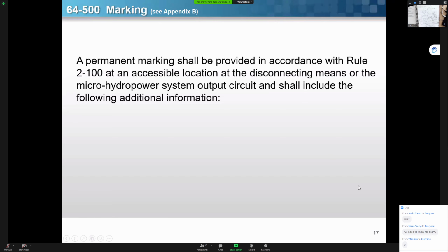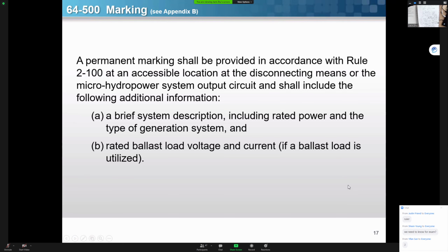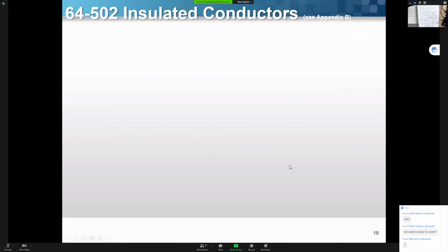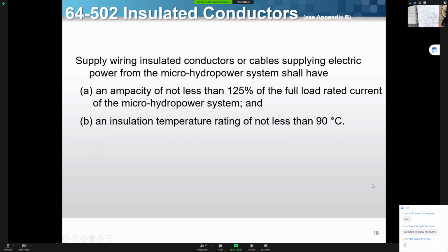This is talking about code rules. We're going to look at the code rules slightly later altogether. Here is something when we're talking about code rules, you will know. When you guys learned about motors in third year, you always learned the conductor capacity for continuous load has to be 125% of rated motor load, right? Here, the same thing for the generator, the conductor capacity is at least 125%. But in this situation it also requires the conductor insulator temperature rating to be 90 degrees.